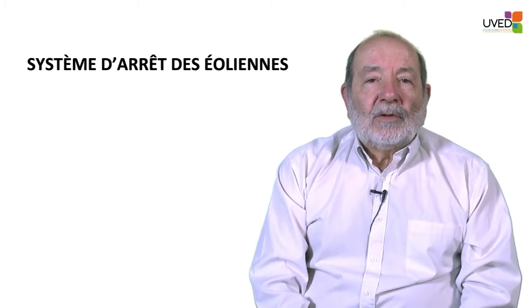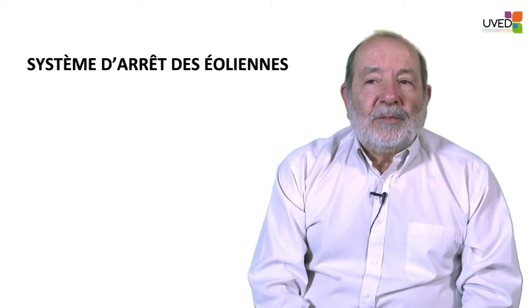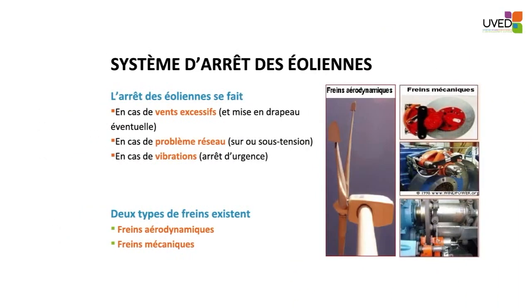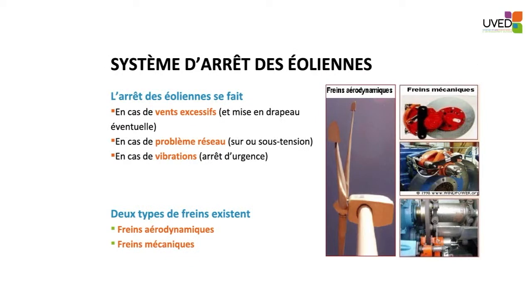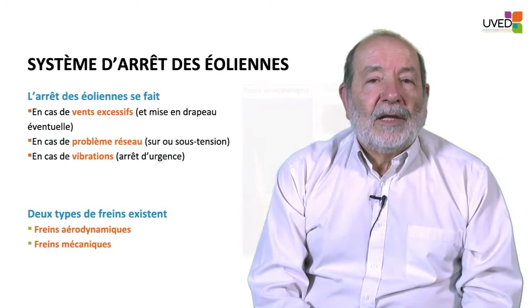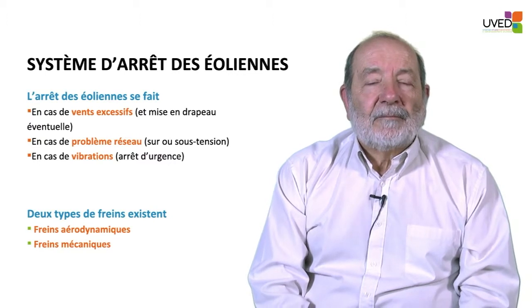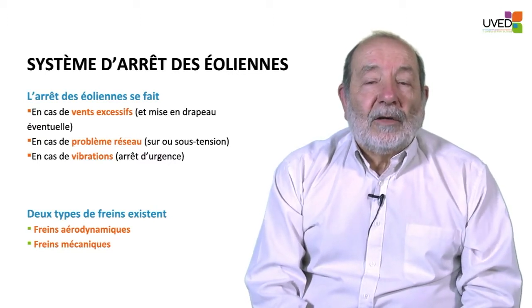This is also what happens with American windmills. The shutdown systems are of two types: windmills will be stopped if there is too much wind — more than 25 meters per second — most windmills will be feathered, and also if there is an electrical power supply problem or too many vibrations.